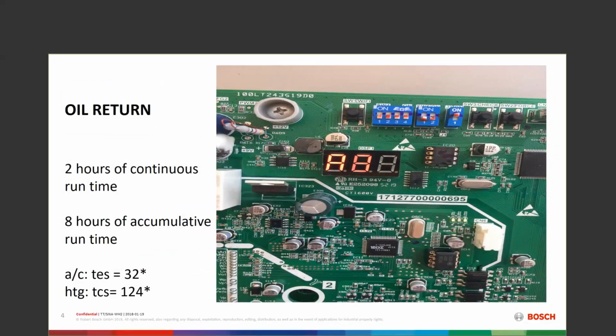If I have a system that has been running for 2 hours, and we've seen this in our training carts and training units on the trailers, basically running as we do the training, 2 hours of constant run time and basically not satisfying the thermostat, I will go into oil return. Oil return will be basically for 5 minutes. If I don't satisfy the thermostat during that particular time, if I don't reach the temperatures that I need to see, I will continue that for another 5 minutes, but never more than 10.